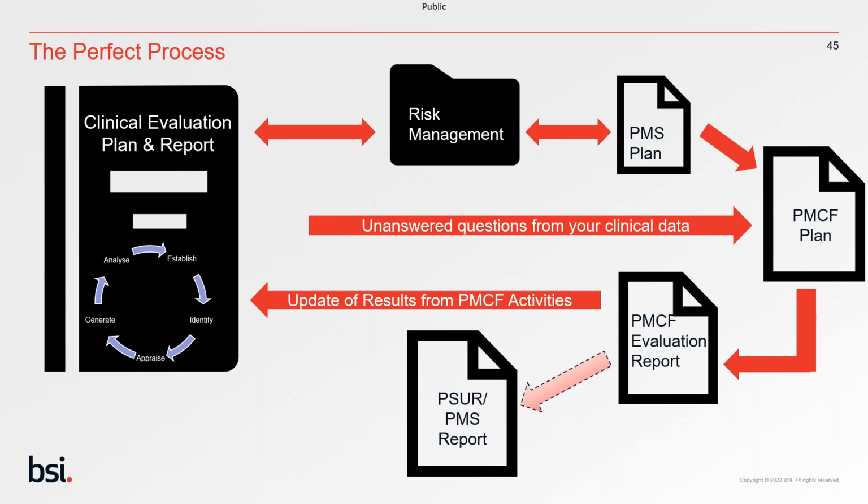The main findings of PMCF need to be identified there, along with, of course, the outputs of your post-market surveillance plan. And really the output of your report should also feed into your risk management to make sure that your device is continually behaving as it should be in terms of safety and performance. But some of those post-market results need to also go into your clinical evaluation as well.